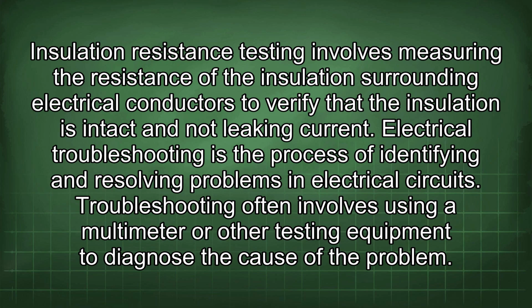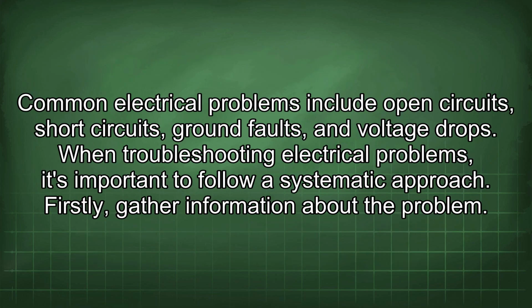Troubleshooting often involves using a multimeter or other testing equipment to diagnose the cause of the problem. Common electrical problems include open circuits, short circuits, ground faults, and voltage drops. When troubleshooting electrical problems, it's important to follow a systematic approach.